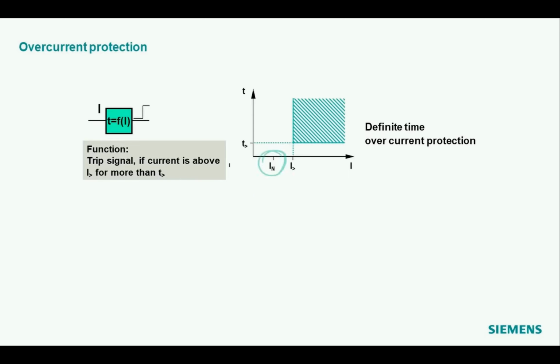This is the load area. That would be the nominal current, maybe of our transformer or whatever. We have a certain security margin. And as long as the currents are somehow in this load area, the trip time is infinite. That means we have no trip. As soon as we are above the setting limit, we start our timer, and then we will issue a trip if this condition remains there for a given time, a time which is given by the user.